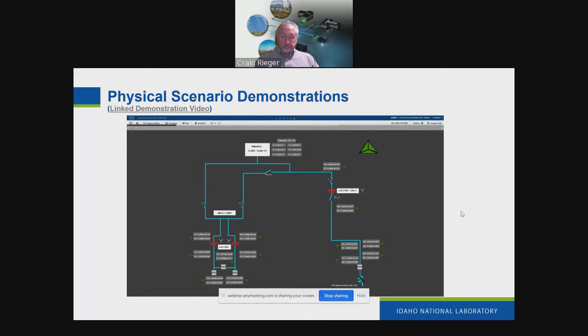The distributed state estimator used in this project has 2 levels. The Tier 1 estimator is executed at the substation level using local measurements. Separate calculations are performed on the low side and high side of the transformer to try to provide more granularity for detecting anomalies. This is able to handle much more complicated bus structures than are shown in this system in the HMI. The estimator is able to assess conditions and flag anomalies. These warnings about anomalies are sent to the Tier 2 estimator, as well as to a local HMI that can be looked at by personnel on site.